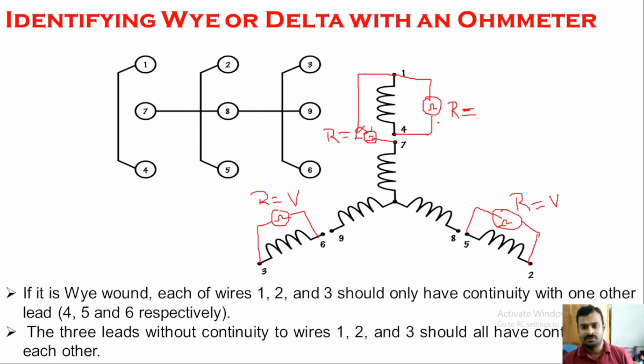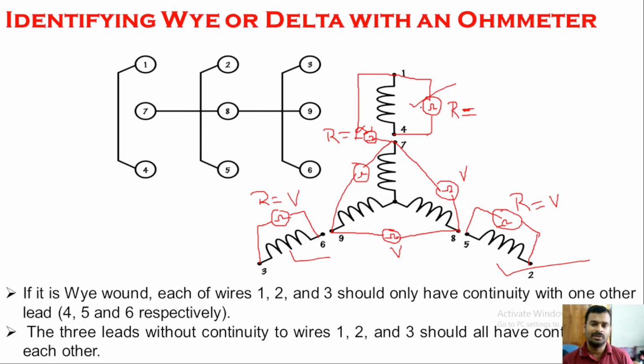So once I get these values, three coils give me a value, and I can almost say that it is a star connection. Now for the final check, there are pairs of terminals where resistance is there, here, here also we found, and here also we found. So the remaining three terminals are left. If you connect the resistance meter between any two of these terminals, you will get values. Here also you get a value, here also, and here also, because there is continuity between these coils. So if you get this combination of values, you can conclude that this is a star connection.